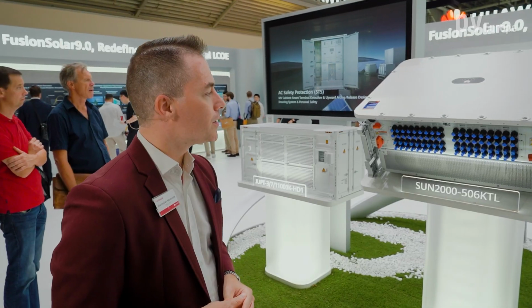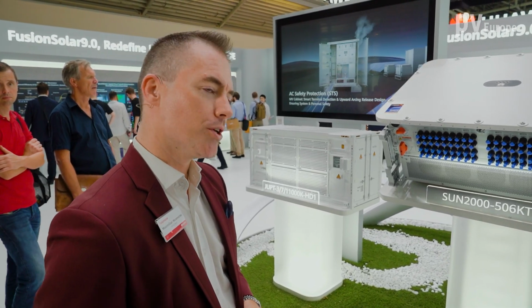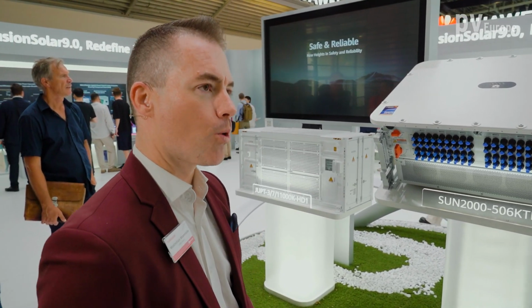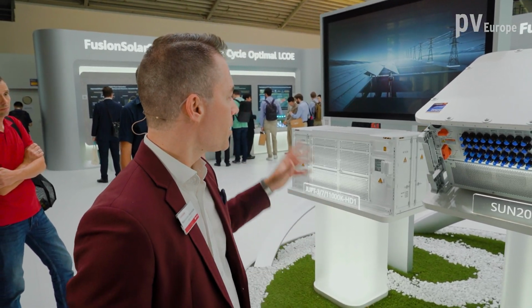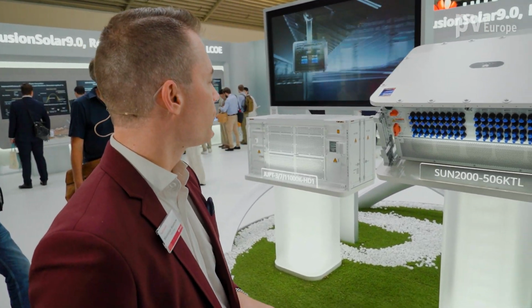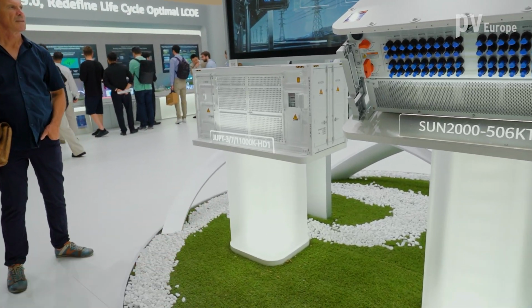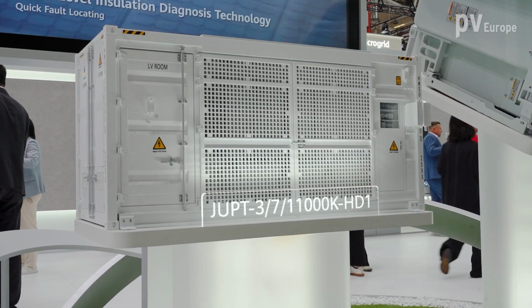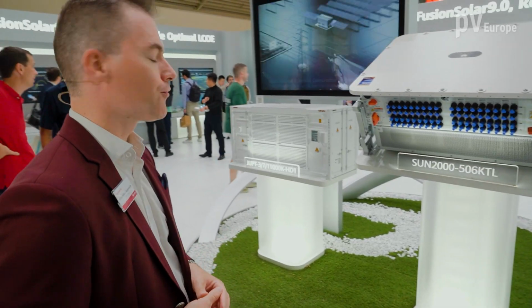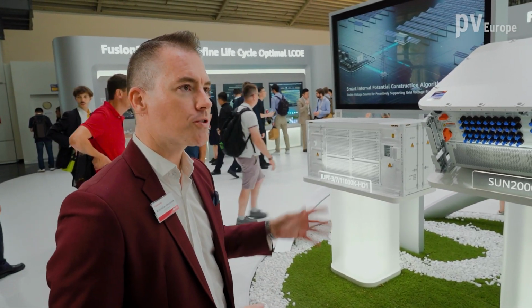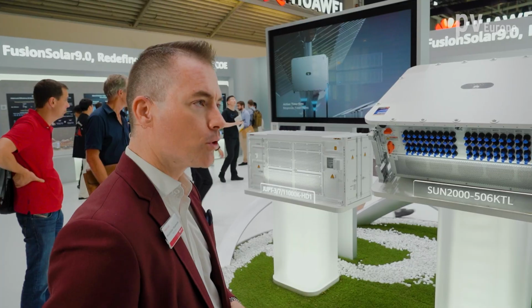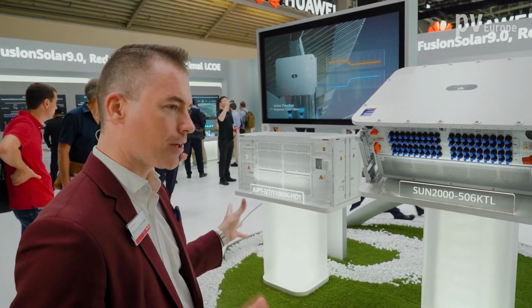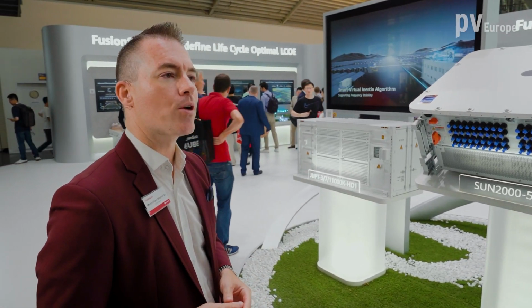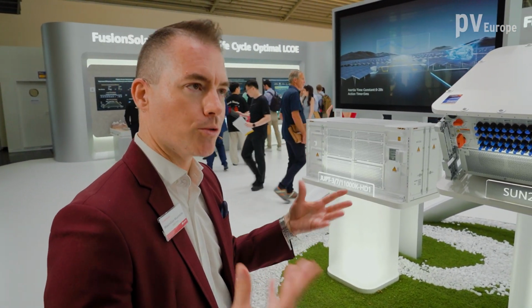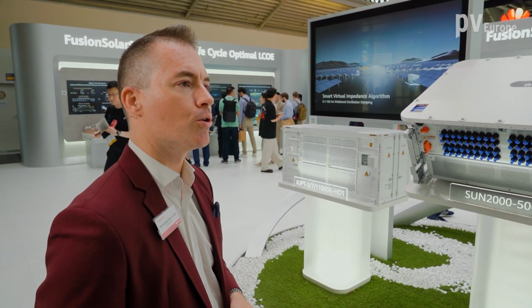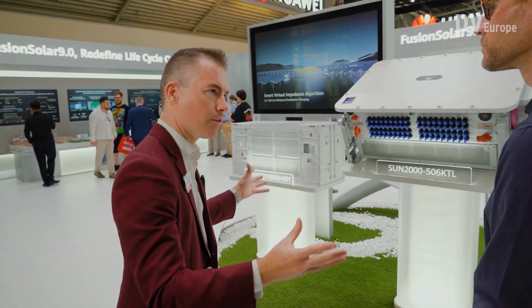Now that the inverter has increased in size, we will also now increase our transformer station. So the transformer station that you used to know from us has been in the power ratings of 3, 6 and 9 MVA. We have now increased that to 3, 7 and 11 MVA. Of course, medium voltage switchgears, fully available in SF6-free technology in the 20 kV line, and additionally eco-friendly transformers with biodegradable oil in case you're utilizing that in an eco-friendly environment.